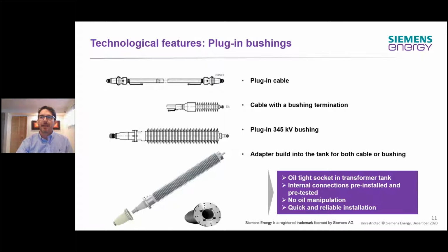And that means to connect both the high voltage as well as the low voltage sides of the transformer, you don't need to open the transformer tank anymore. You don't need to expose the active part of the transformer. So it is an oil tight socket in the transformer tank. It is pre-installed and pre-tested. You don't have to manipulate the oil. It's a quick and very reliable installation.